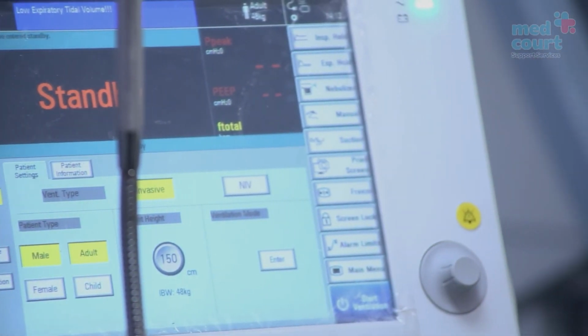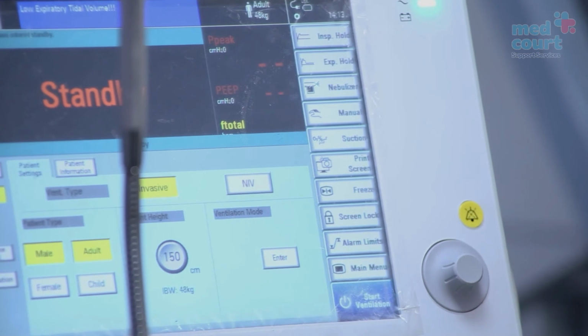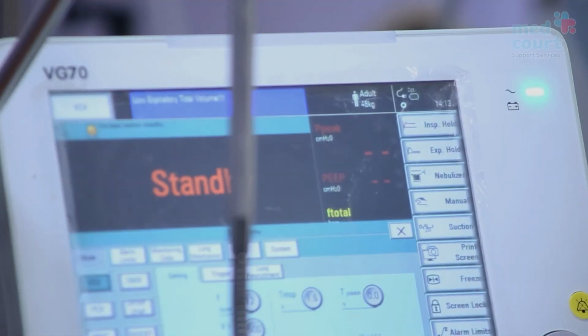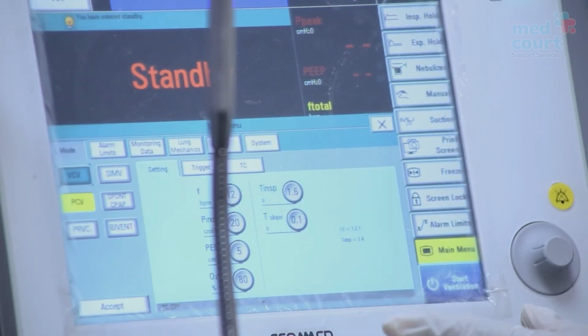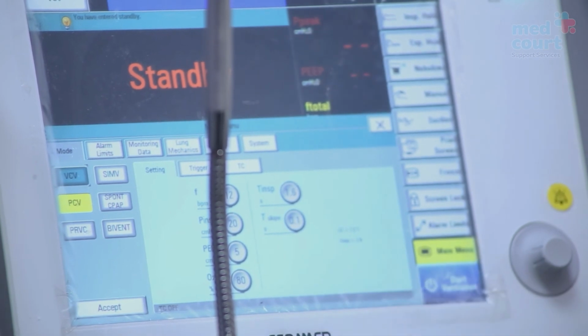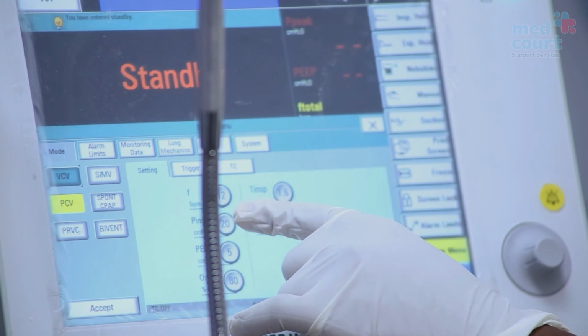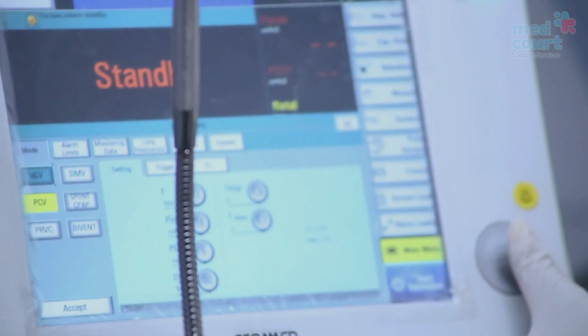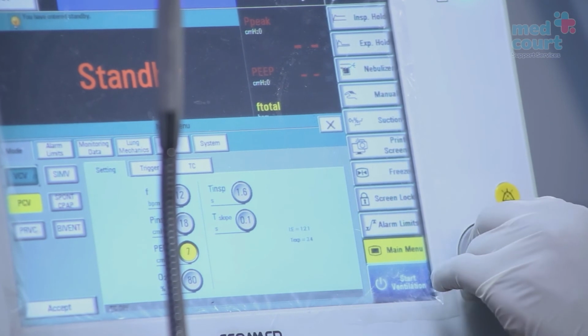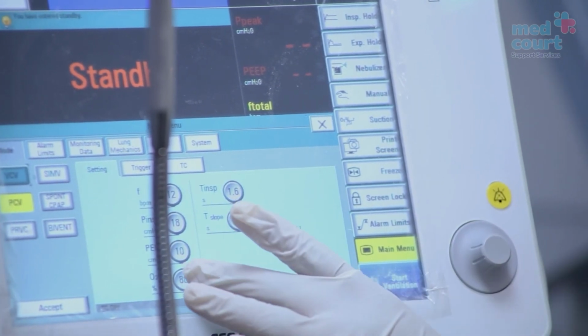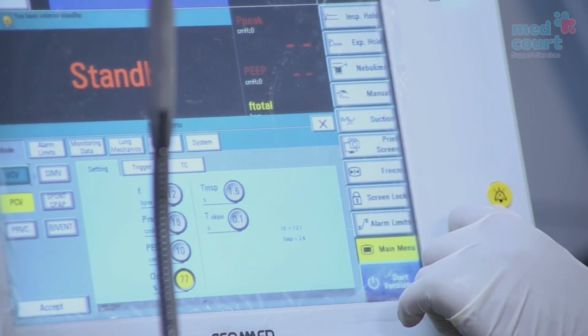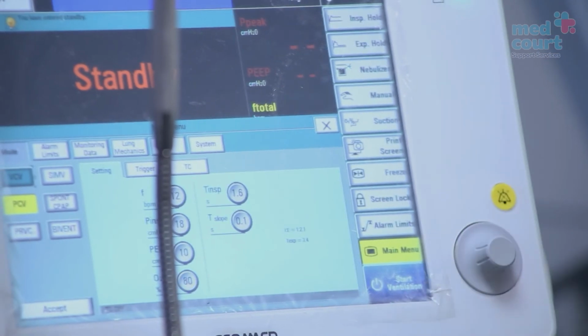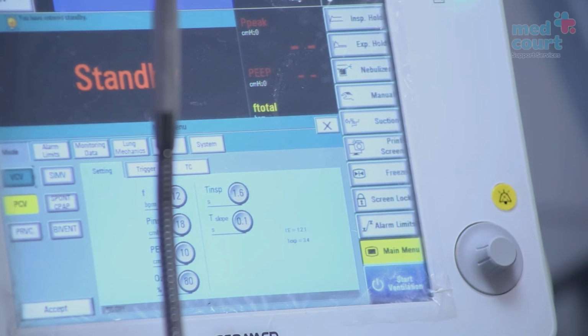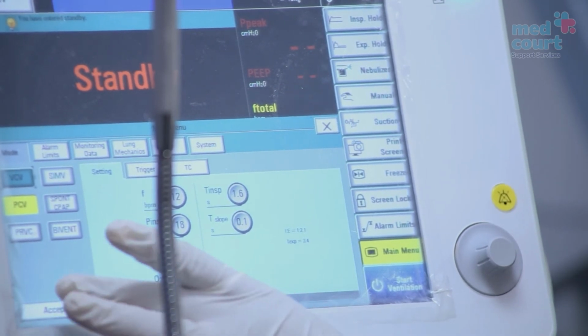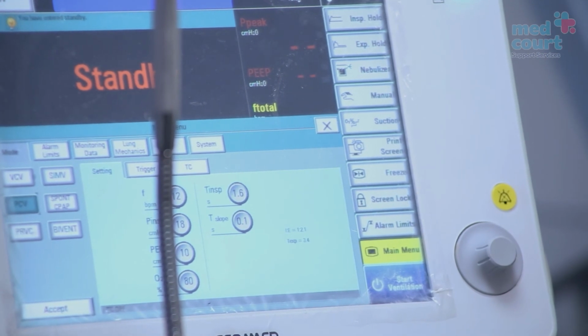For a brief moment, we stop ventilating so as to set the parameters for our pressure control. So we set on our ventilator the pressure control mode, and we set our parameters. For the respiratory rate, we have 12. For the inspiratory pressure, we have 18. So we'll click on it and set it and we enter. For the PEEP, we'll be using 10. And for our oxygen percentage, we'll be using 70. All these parameters are set using the manufacturer specification for this mode. So press our accept key. Okay, and we start ventilation.